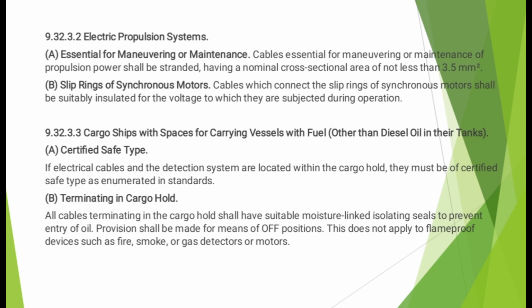9.32.3.3 Cargo ships with spaces for carrying vessels with fuel other than diesel oil in their tank. Certified safe type. If electrical cables and the detection system are located within the cargo hold, they must be of certified safe type as is enumerated in standard. Terminating in cargo hold. All cables terminating in the cargo hold shall have suitable moisture-linked isolation seals to prevent entry of oil. Provision shall be made for means of off-position. This does not apply to flame-proof devices such as fire, smoke, or gas detectors or motors.